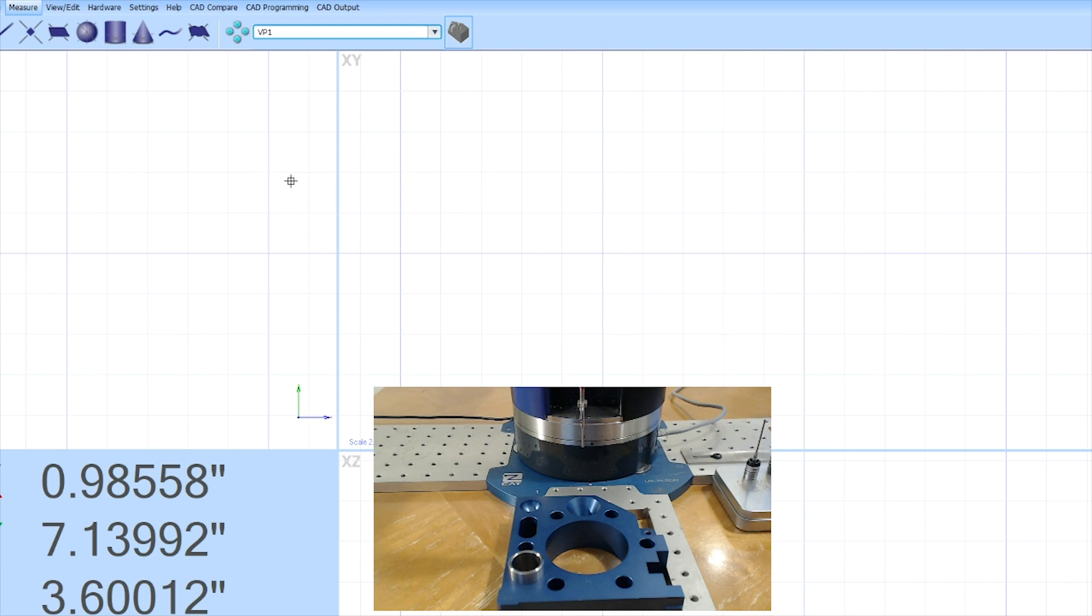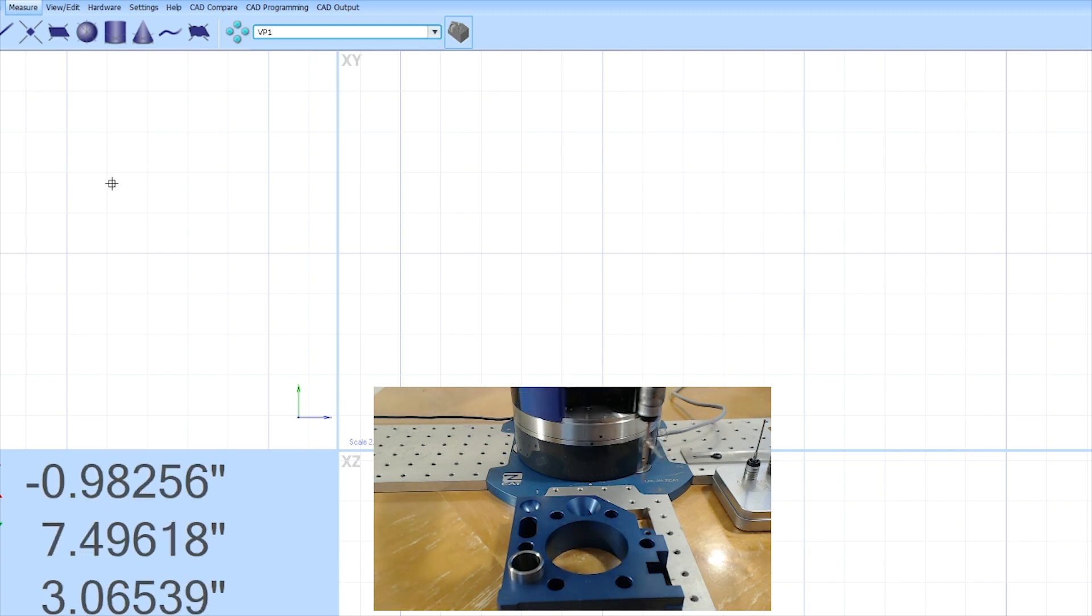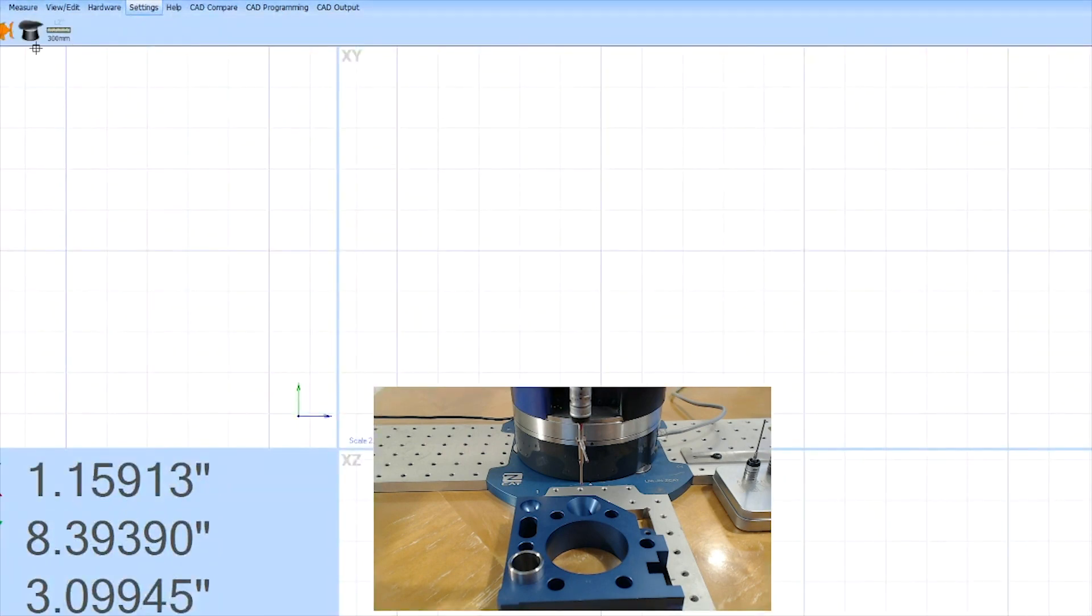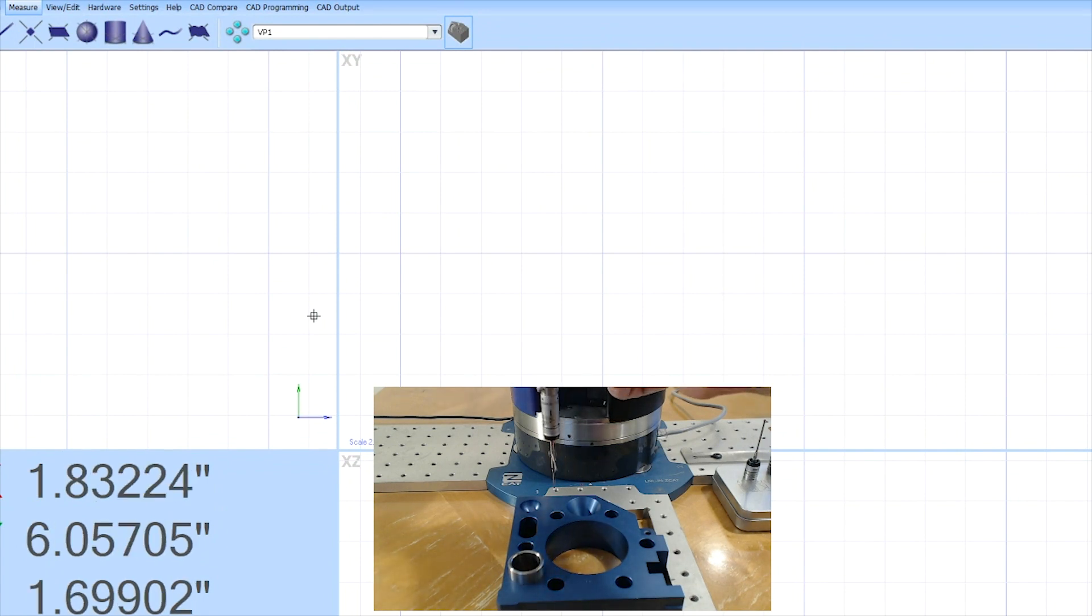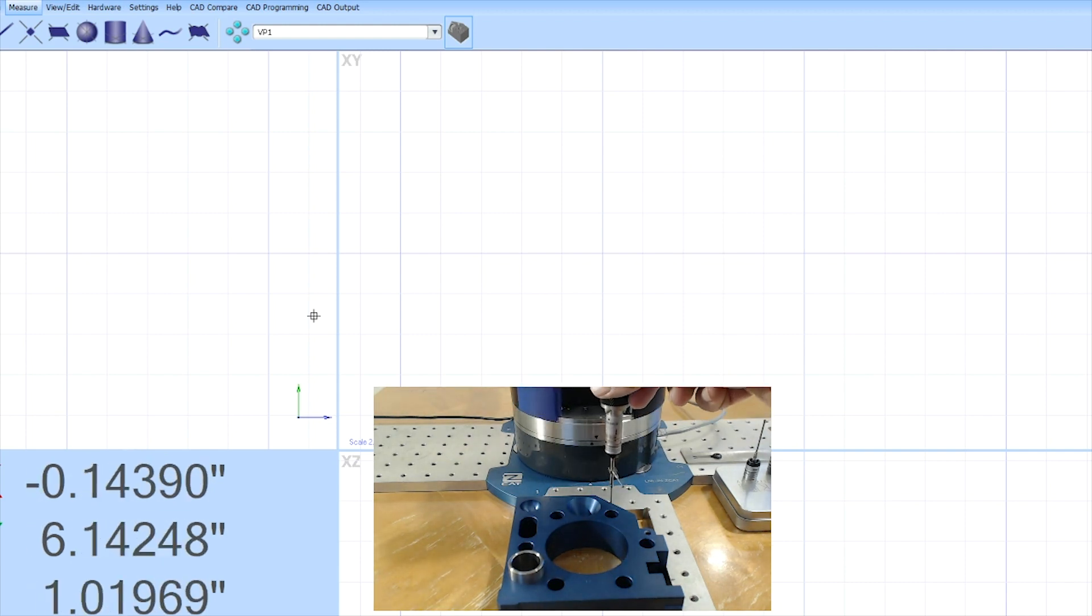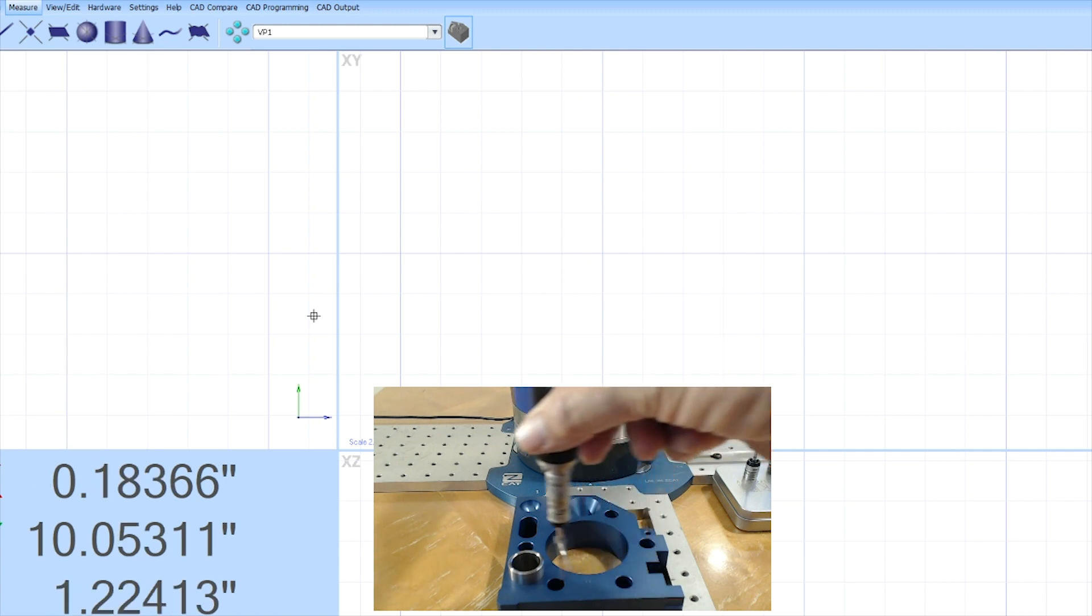We're running the Mark 4 Fowler Fusion software. If I wanted to start writing a program for this part, I can go into our settings and turn on what we call feature predict because it will predict certain features. So I'm going to turn that on and with my vertical probe I'm going to come down here. I'm going to measure a plane on the top of this part. If I measure at least four points it will give me a plane on my software as you can see.